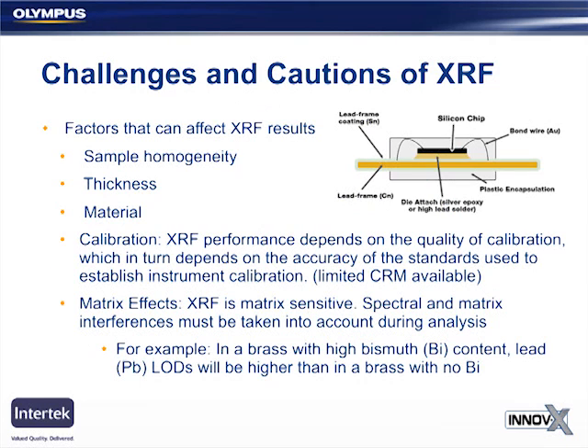Probably the biggest challenge in interpreting XRF results is looking at inhomogeneous samples. So the analyzer's calibration normally assumes that the material being tested is uniform and the elements detected are distributed homogeneously. When testing a material made up of multiple different materials, the XRF result may not represent any one material tested. So in order to deal with that, you want to test at the homogeneous level as much as possible, as high up in the production stream as you can. For inhomogeneous samples, your results are usually qualitative. You can see what elements are present, and you can judge how much relative to other similar sample types, but the ppm result that you see on the screen may not apply to any one material in that sample.